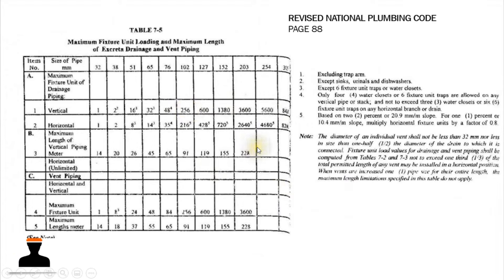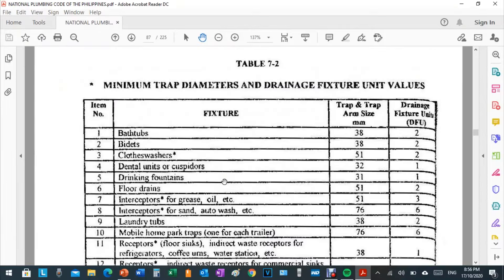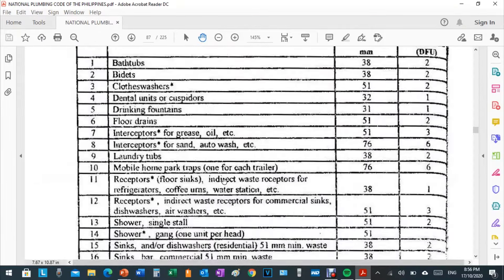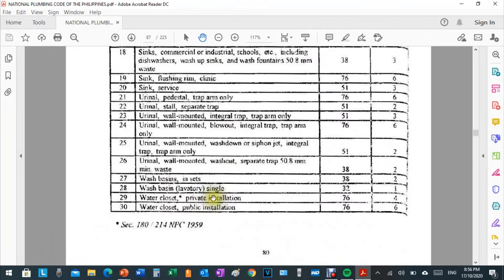Let's apply this table in actual design. Example number one: determine the diameter of the horizontal, vertical, and vent pipe that serve two private water closets, two lavatories, and two floor drains, and compute the maximum length of the vertical pipe and vent pipe. First, let's compute the total drainage fixture unit by going to Table 7-2. We have three different fixture types: water closets — private installation.